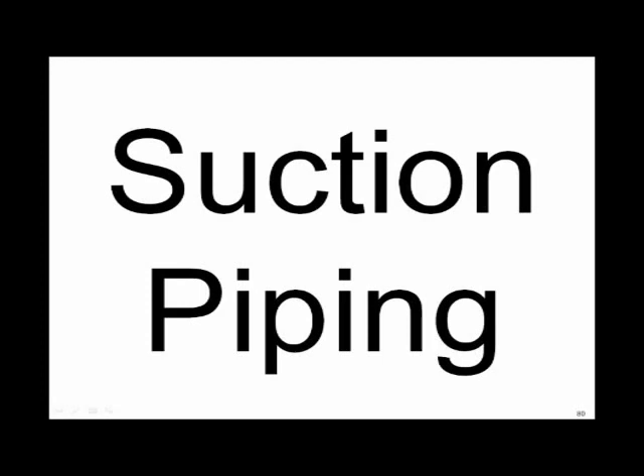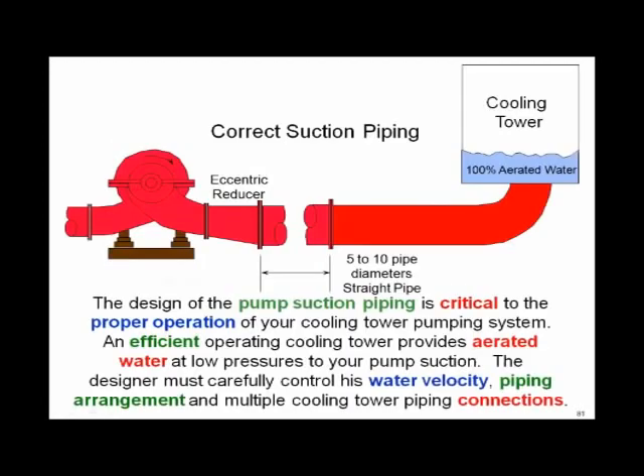Now we'll look at suction piping. Piping is something that we wanted to make sure we looked at, and we've covered a lot of pieces of it, but we're talking about cooling towers, so we've got to look at pumps a little bit and suction piping. When you do that, keep in mind that a cooling tower aerates water. So the water in the basin of a tower is full of air. It's as full of air as you can get it. In fact, the 100% efficient tower would be just full of air. It couldn't take any more. So if I drop the pressure on that water in the basin of that tower, air's going to start popping out. So my suction piping has to take into consideration the fact that I might have air in it. How would I handle it?